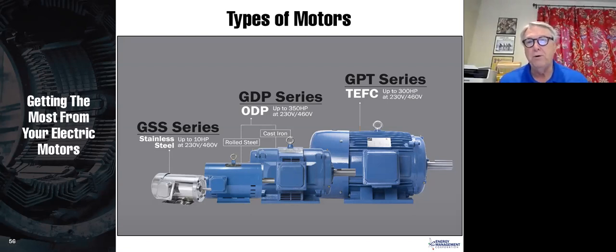Open drip proof, of course, meaning if you get some drips of water on that, it's okay. They won't go into the motor. And open means the air goes through the motor. In this case, we have a cast iron motor. It's better because a cast iron motor is extremely stiff, and a cast iron frame is going to break before it will bend. So it holds those bearings in perfect alignment, and you will get much longer bearing life. And we will talk about bearings in a moment, because those are the #1 cause of motor failure.